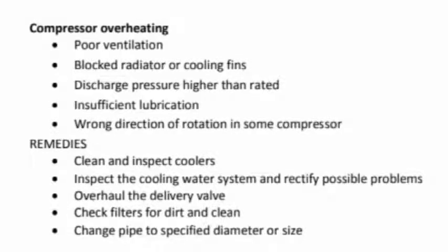Compressor overheating. Possible causes: number 1, poor ventilation. Number 2, blocked radiator or cooling fins. Number 3, discharge pressure higher than rated or normal. Number 4, insufficient lubrication. Number 5, wrong direction of rotation in some compressors.